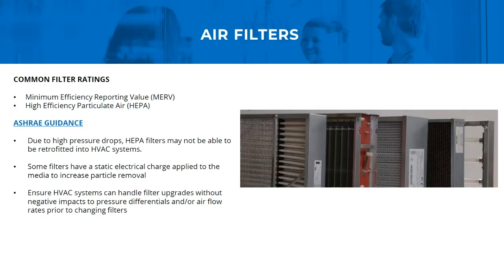If you have a facility currently that has a MERV 8 and the system is only designed for a MERV 8, there are specific, statically charged filters that can be applied to a filter media to bring the MERV rating up. But before any of these changes are made, you need to go back to your manufacturer's spec and ensure that HVAC systems can handle the upgrade without any negative impacts on the equipment or airflow. One of the biggest challenges here is to not interrupt tenant satisfaction with the temperature of air that we're providing. So filters have become a big part of what we do, and even though it's last on our slides here, it's definitely one great consideration that we have.